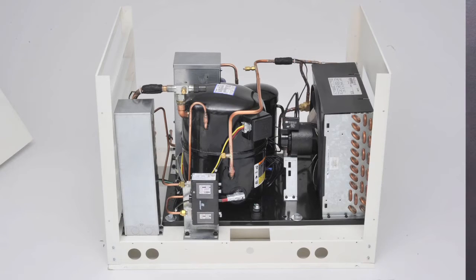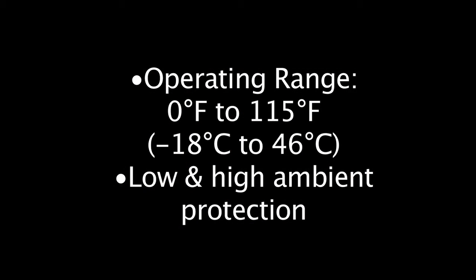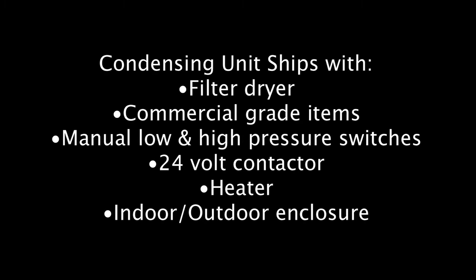The operating range for the condensing unit and the system in general is from 0 degrees Fahrenheit up to 115 degrees Fahrenheit. It has low ambient protection as standard offering, standard equipment, as well as high ambient, standard offering. I want to point out that the condensing unit ships with a filter dryer as part of a complete package.